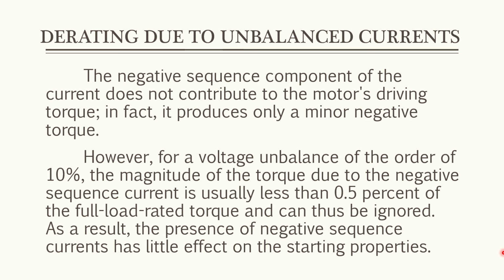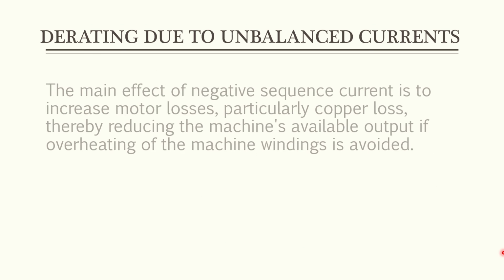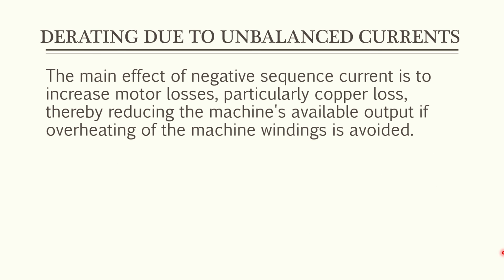So, when we're talking about starting properties, yung paano mag-start yung isang motor, the negative sequence current or the unbalanced current has a little effect on it. But the main effect of negative sequence current is to increase motor losses, particularly copper loss, thereby reducing the machine's available output if overheating of the machine windings is avoided.